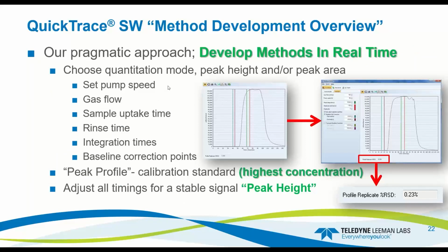So here's an example. You set your pump speed, your gas flows, your sample uptake time, your rinse time, your integration time, and you just run the high standard. So it looks like this, and you very simply go in and adjust all this stuff. And then on the bottom, it's going to give you a percent RSD for the peak profile. And then you can go ahead and grab that and send it into the log. So you can adjust all the timings there in real time. And then you can repeat it a second time to make sure it's still the same. So it's really a nice feature.